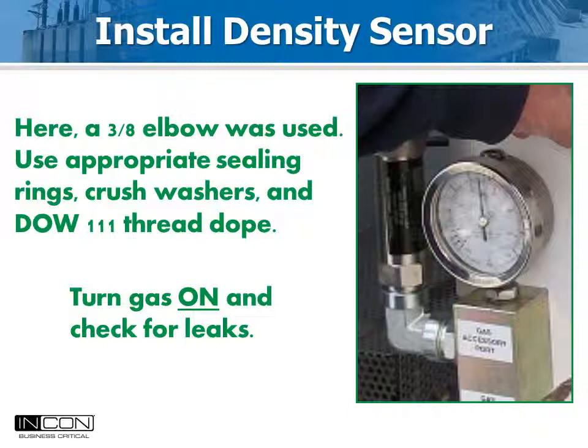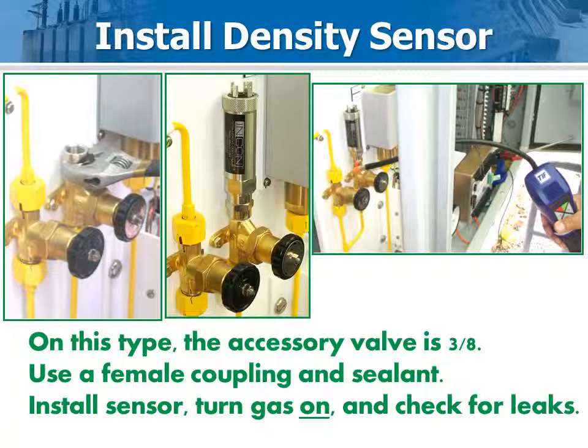On this model, a 3/8" female elbow and 3/8 to 7/16 male adapter was used to connect the density sensor. For this breaker, a spare valved connection was available. The valve had a 3/8" male end, so a 3/8 female coupling was used to connect the sensor. Here, a gas sniffing tool was used to detect leaks after the gas was turned on.